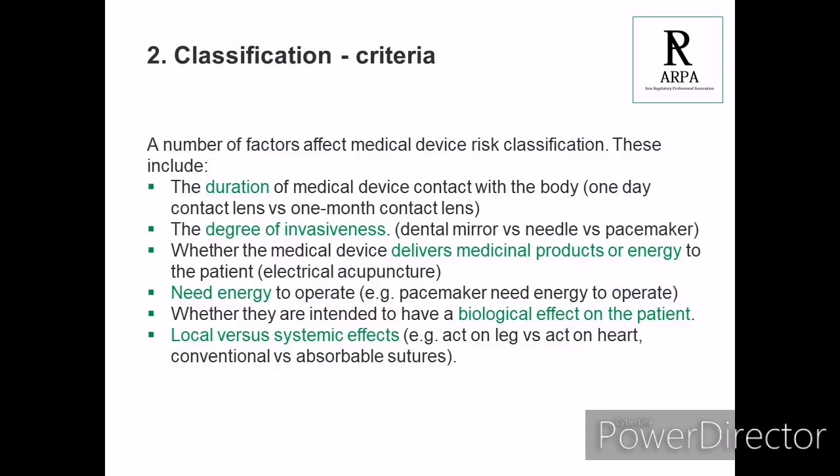So how do you know which risk level your product belongs to? There are a number of factors that affect medical device risk classification. For example, the duration of medical device contact with the body. Of course, a 1-day contact lens will have less risk than a 1-month contact lens. The next one is the degree of invasiveness, like how the device goes to or even goes inside your body.